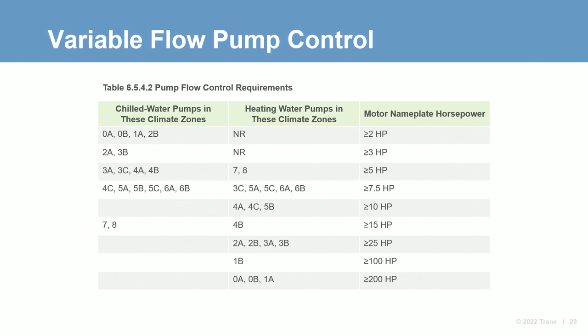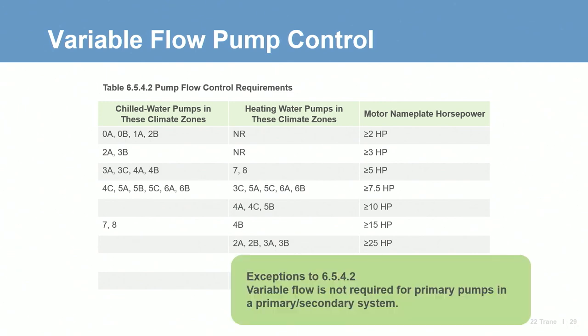The section pertaining to pump flow control essentially requires variable frequency driven pump performance once a system has three or more control valves and once the collective pump horsepower rises above a threshold based on climate zone and whether the pump is used for heating or cooling. In a chiller heater system that uses the same pumps for cooling and heating, the more constraining threshold governs. For this reason, and for better control in all modes of operation, pumps are equipped with variable frequency drives in all standard configurations. Note this does not necessarily mean variable primary flow, so decoupled pumping is still acceptable.